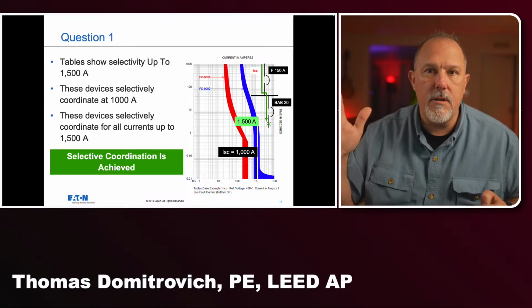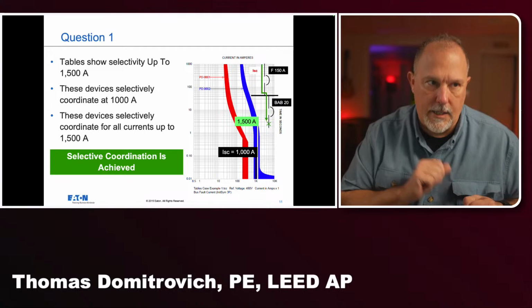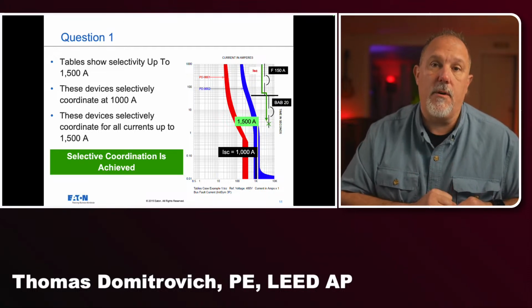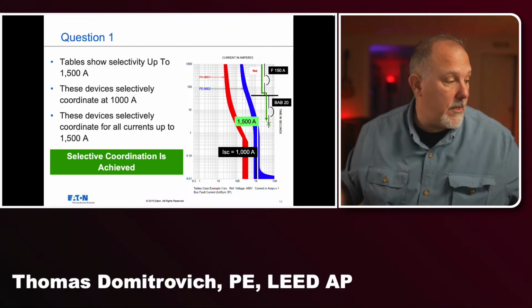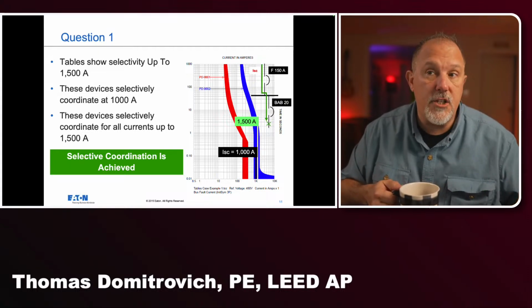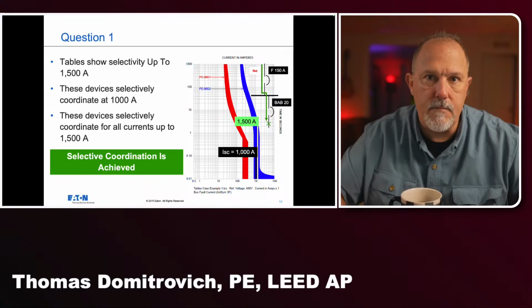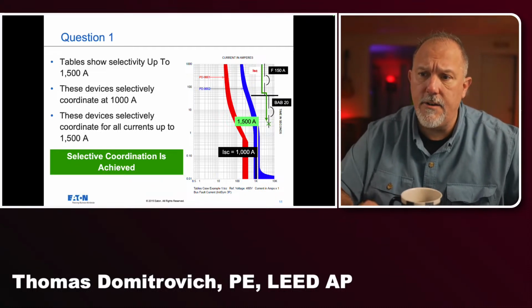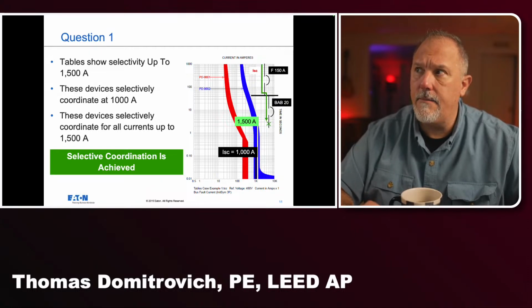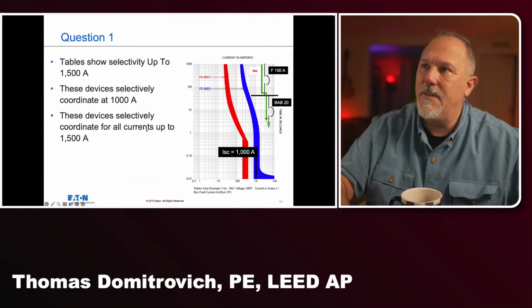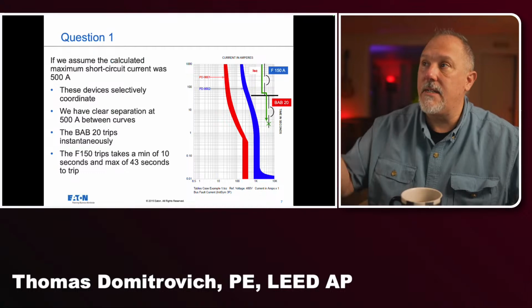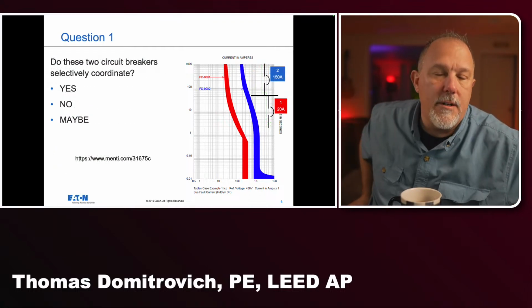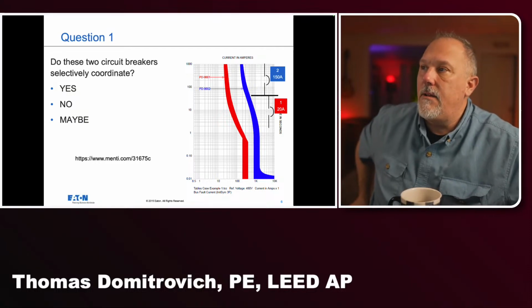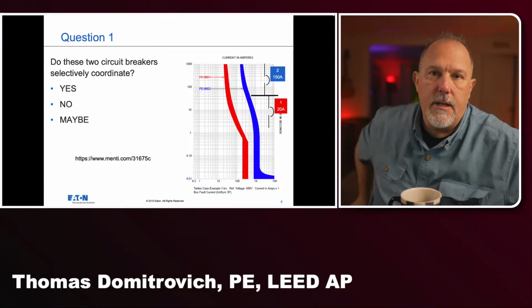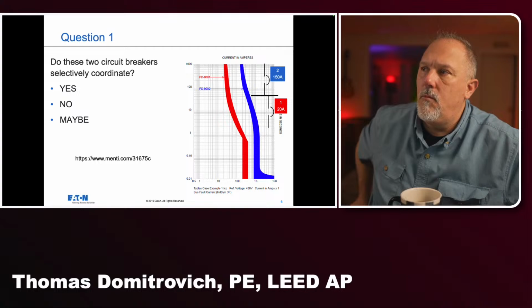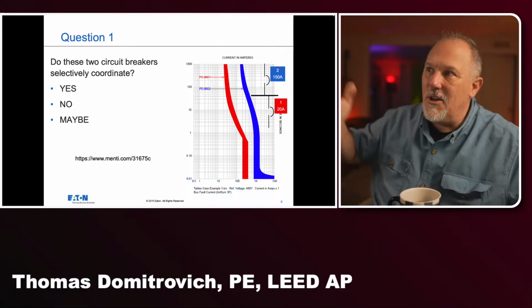That is not an appropriate assumption. It could get you in trouble, and it has gotten people in trouble. I have seen selective coordination studies that aren't selectively coordinated, and by very smart people. It's just because of the way they were taught. I put these two curves for an engineering friend of mine who's very sharp. This was a real world example. I had somebody send an email out and say, hey, I love these two breakers. Look how great they selectively coordinate. And my response was, well, what's the available fault current? And they said, what do you mean, what's the fault current? I said, well, I need to know the fault current to know whether or not they selectively coordinate.